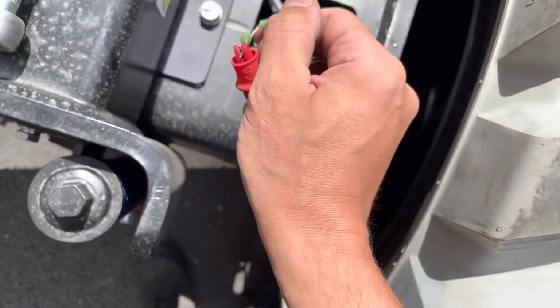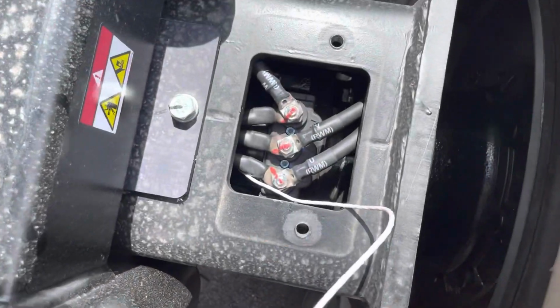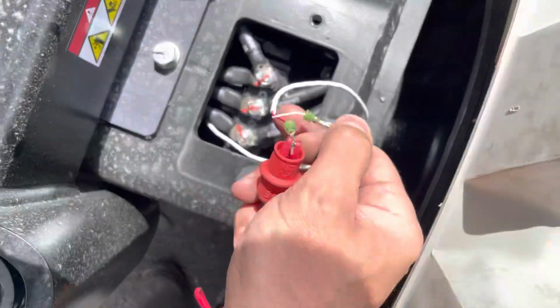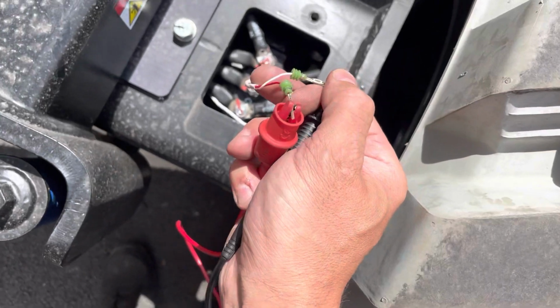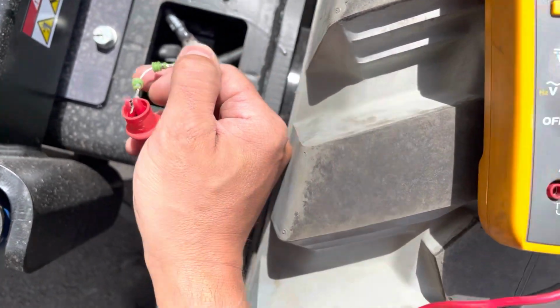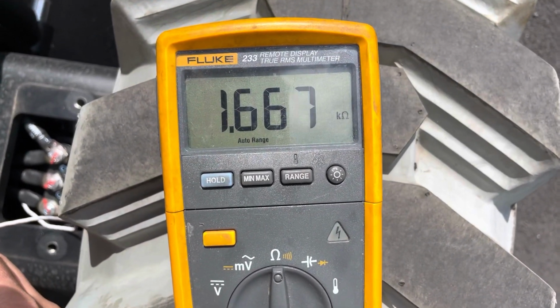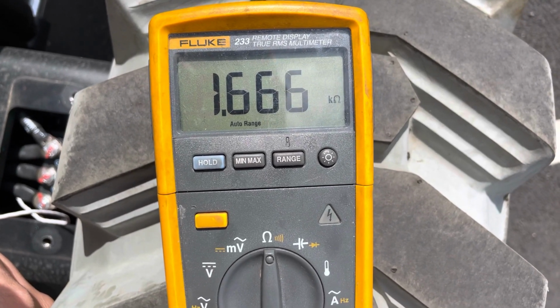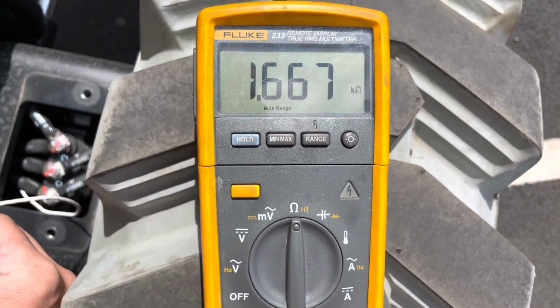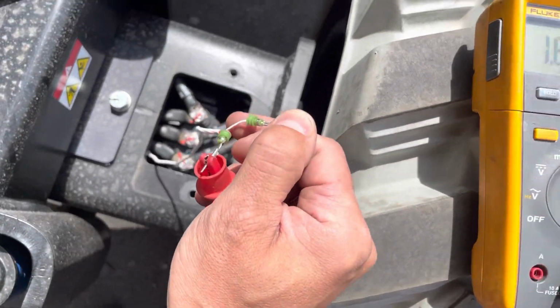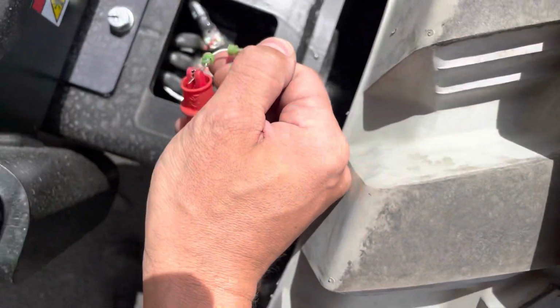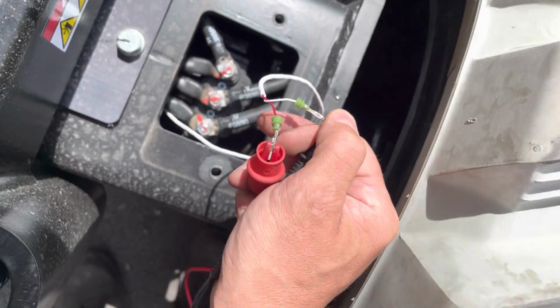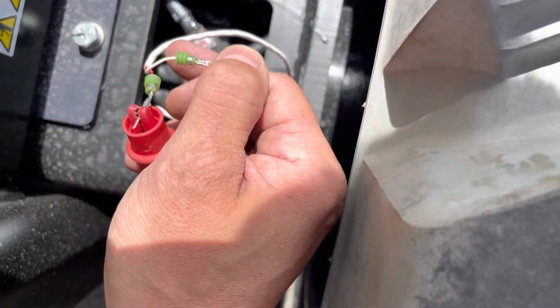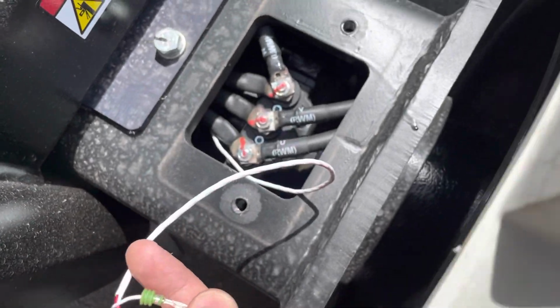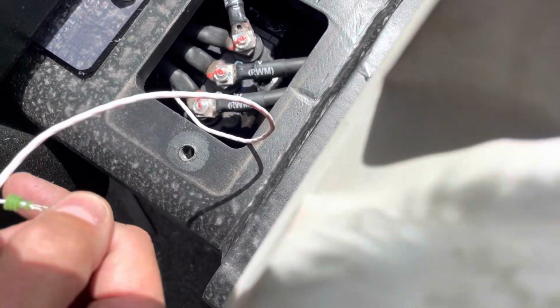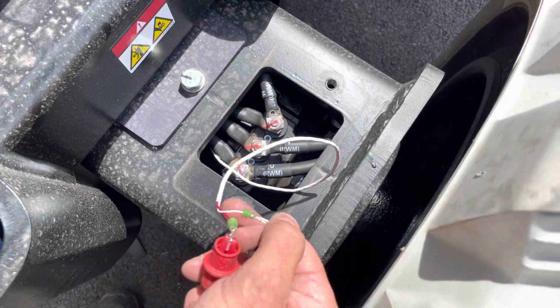So just remove the plug for the top here. So you take the top cover off and you can get access to the wire, this temperature sensor wire, so you can see. I'm measuring resistance again, just double check, and look at this, 1666 ohms. Okay, so I moved the wire around and the resistance slightly increased. I don't think it's a problem with the wire. The crimping all looks good, so we're gonna have to possibly come and replace the motor, because the sensor goes inside the motor. Cannot get to it to remove it.